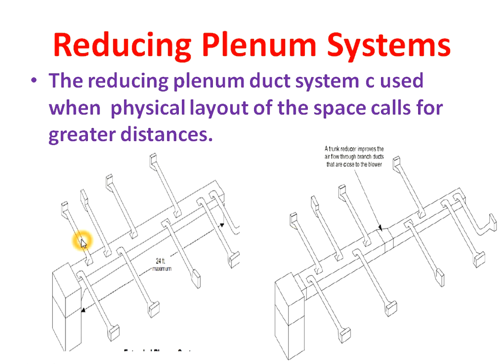If we increase the main duct length beyond 24 feet, there will be less pressure in the branch ducts closest to the AHU, and there will be high pressure in the branch ducts at the far end of the main duct. To avoid this drawback, we use the reducing plenum system.